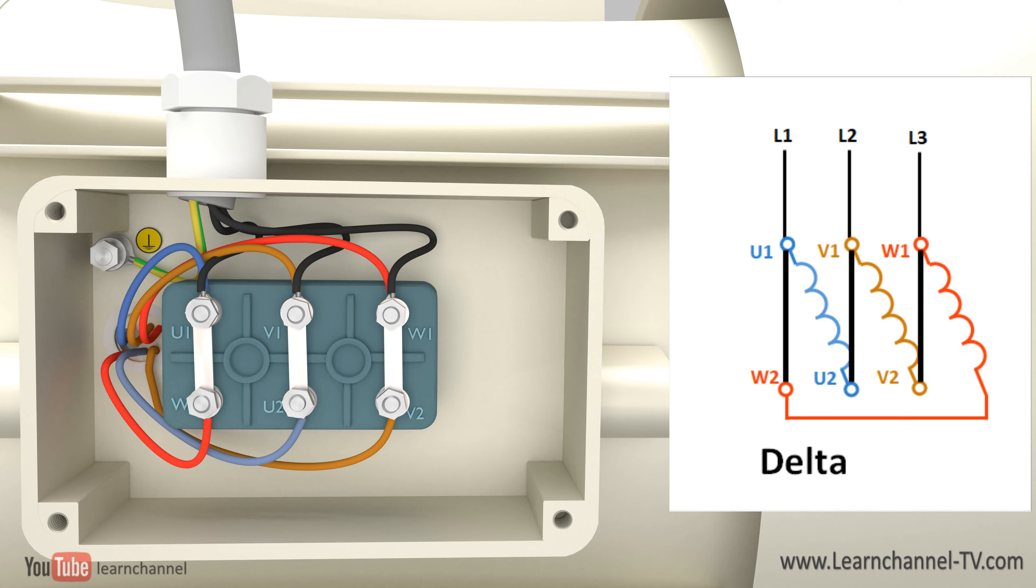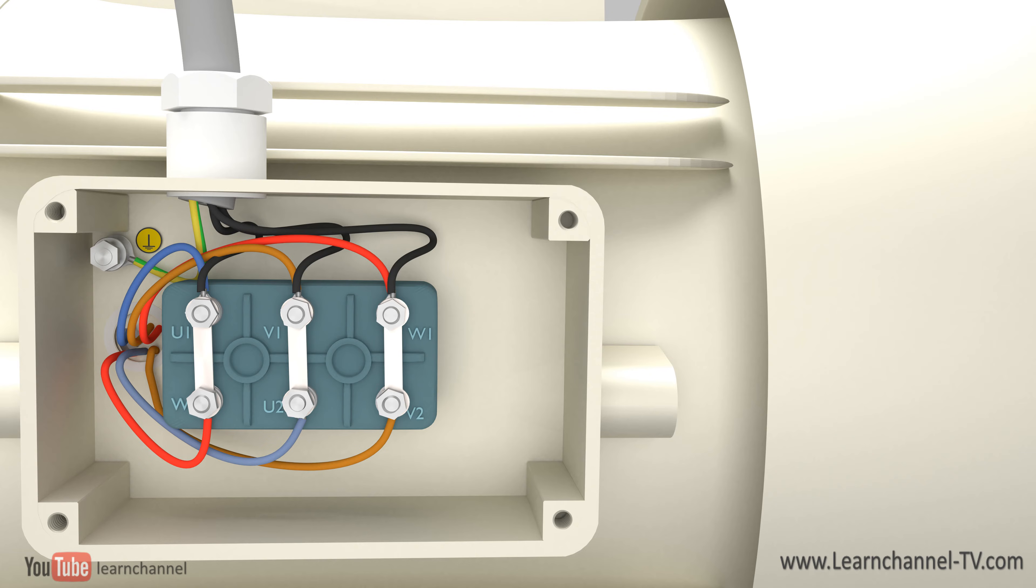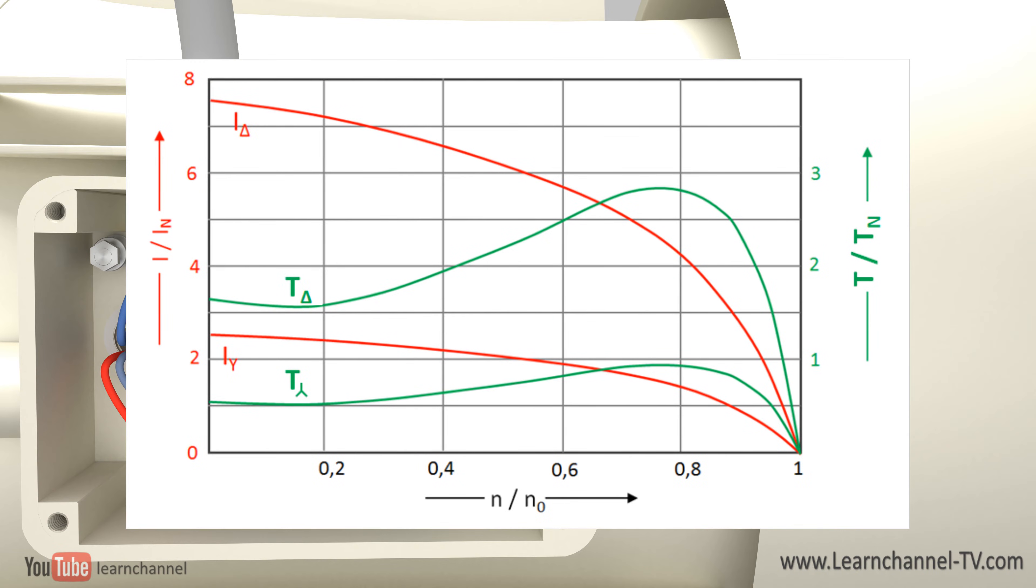You should know that the conductor current in star is only a third as in delta. Unfortunately, the torque is also only one third as in delta. Be aware of this when you start the motor under load.